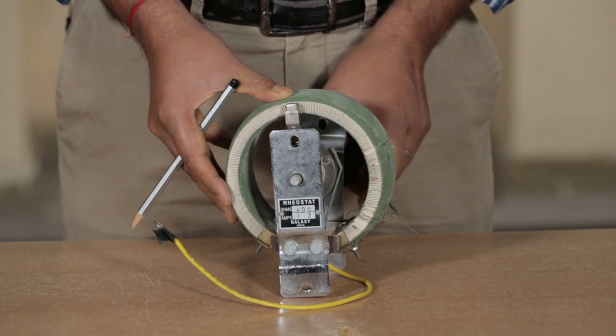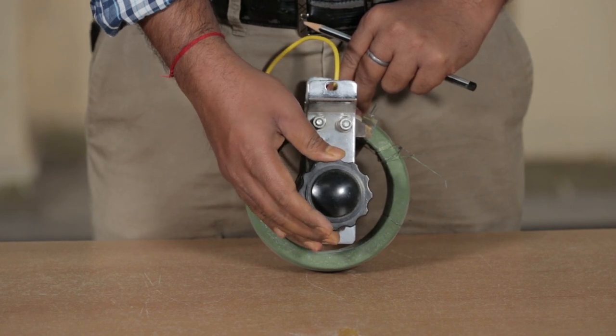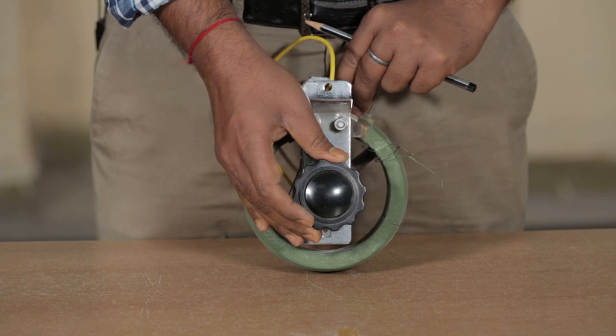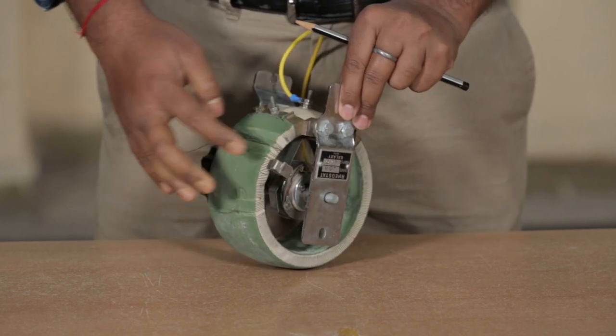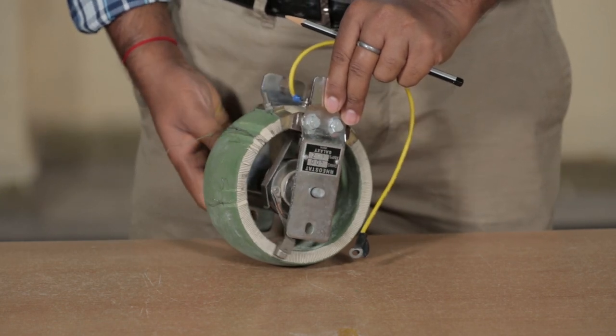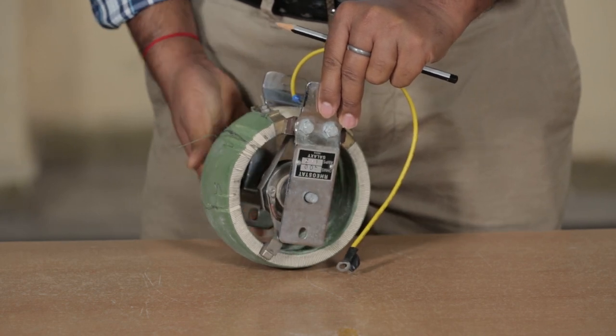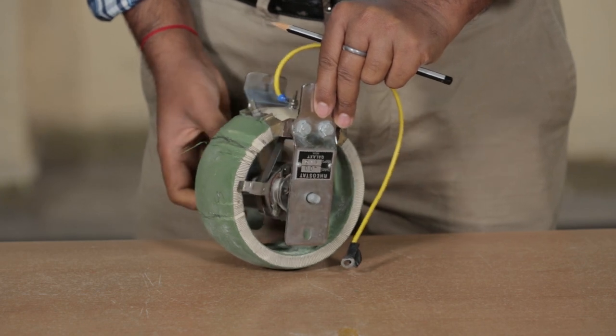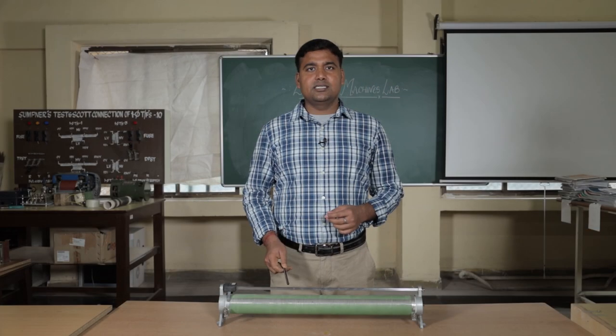In order to gather speed and maintain it at the rated speed, we have to turn the knob and bring it to the maximum position. To vary the speed of a DC shunt motor, we vary the field current by varying the resistance of the field using this device. We have a knob which we can turn so that the resistance is added or reduced. When the resistance is added, the current is reduced. The field current is varied by turning this knob, and if the field current is varied, we can control the speed of the DC shunt motor.